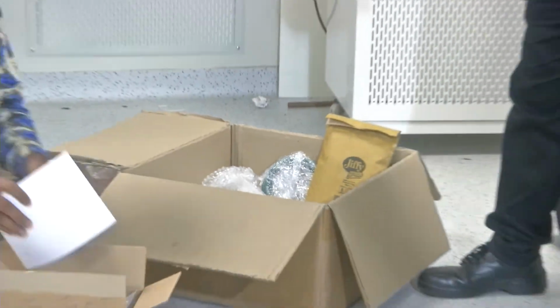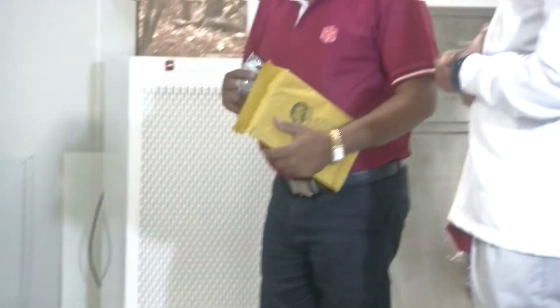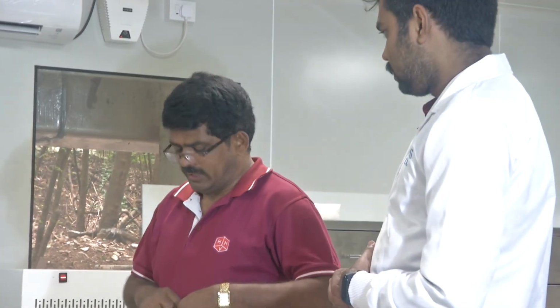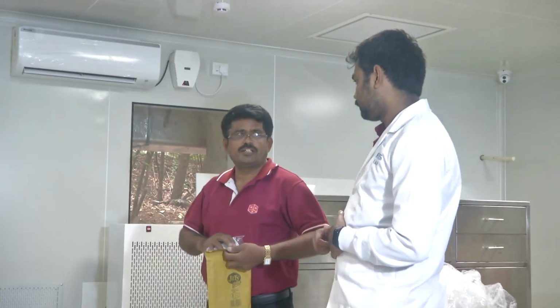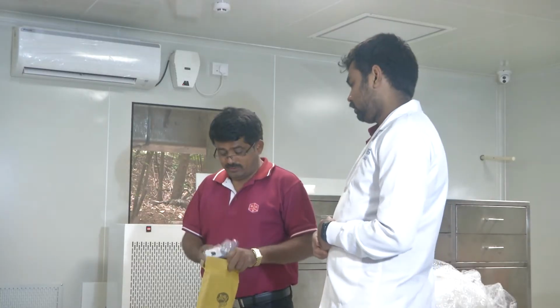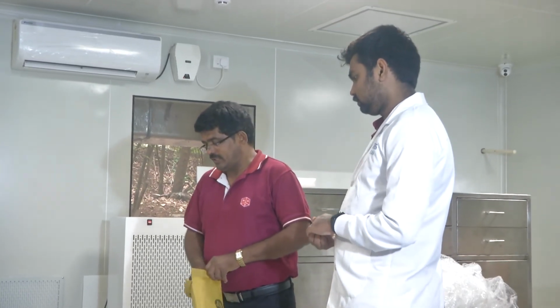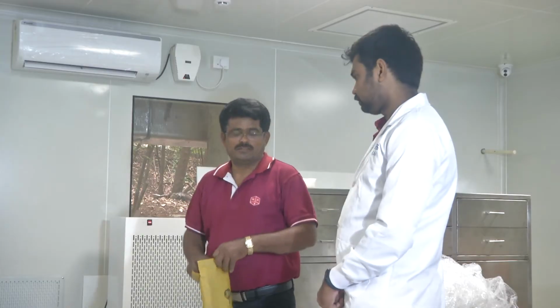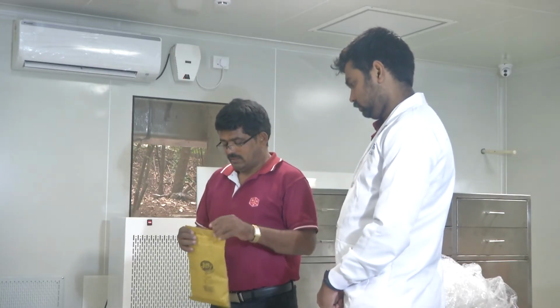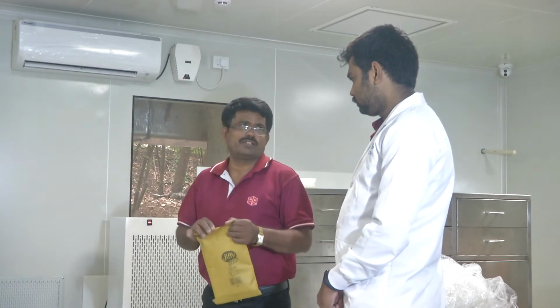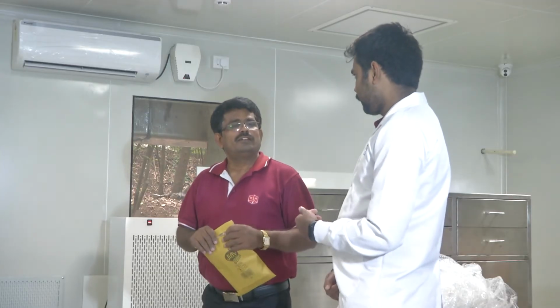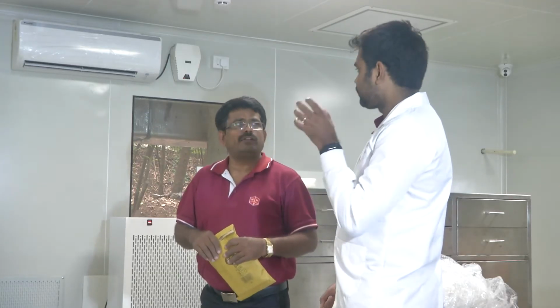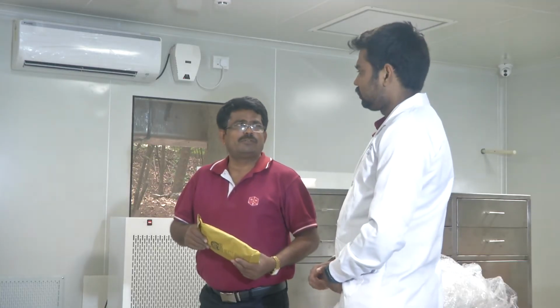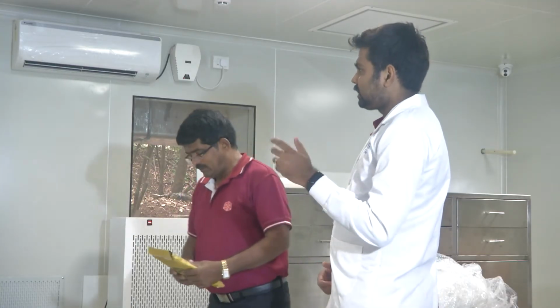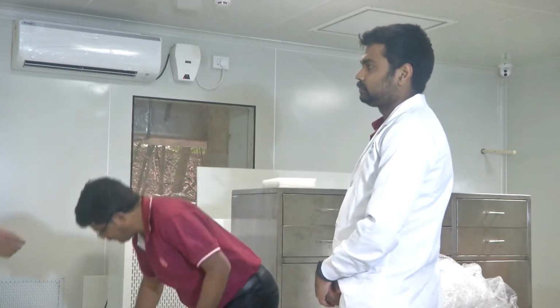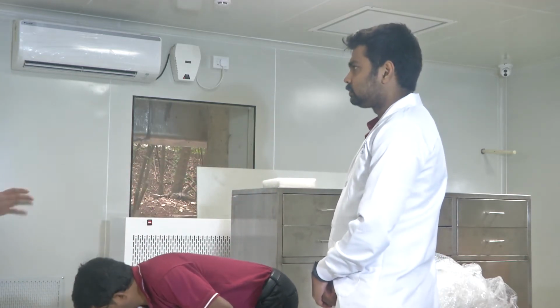So what is the lifetime for these gauges? Like how often do we have to replace them? Nothing fixed. If it malfunctions, you can do a recalibration. So if there is any major problem or the gauge is not working, you can replace it. Once in the year it should be calibrated. Okay, and it will be sent back to the office? We have in-house calibration facility. So we will remove the gauge and send it to you, you calibrate and send it back.